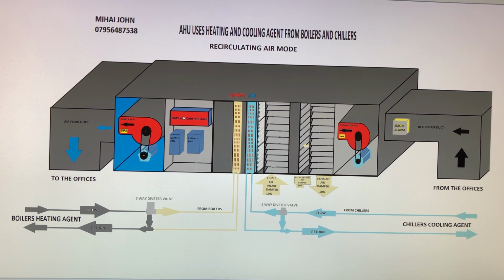Now, in this case, the building management control will sense the temperature outside. If outside it's cooler than inside, it's winter, it's very cold, but inside the store I have a lot of fridges, which can make a lot of problems inside. The temperature can be very low. But let's say it's very cold outside, I have 10 degrees outside, and inside the building I have 16 degrees. Obviously, I don't want to bring too much fresh air. I bring the minimum quantity of fresh air approved by the law to overcome the CO2. And I'm circulating the rest of the air, 90%, and I will exhaust only 10%. That's all I'm going to do.